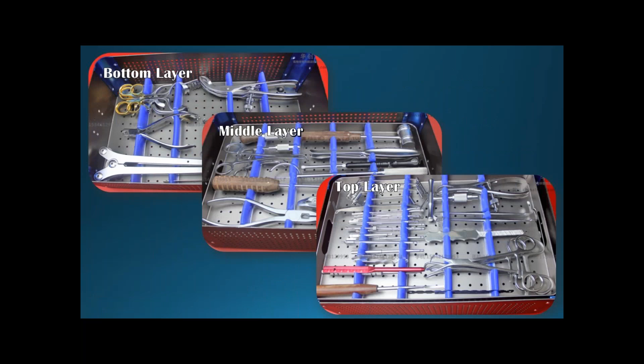When you have wrap sets, basically how wrap sets work is that when they're exposed to steam, those little holes in them act like pores in your skin, and so they open up in relationship to steam, and then they close up. And so when they come down to temperature, you can't touch these in between, when they're not at room temperature. It's very important. And if you have problems with holes in your wrap sets, they do have transfer trays that you can use to help, which is what I have a picture of here.